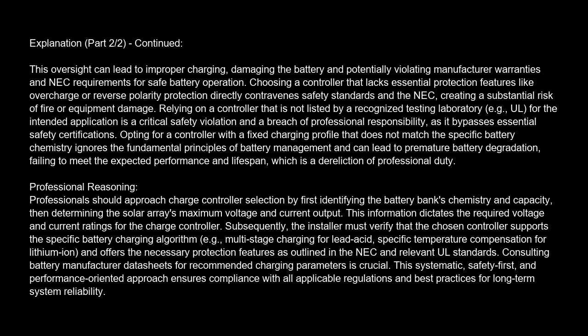Subsequently, the installer must verify that the chosen controller supports the specific battery charging algorithm, e.g., multi-stage charging for lead-acid, specific temperature compensation for lithium-ion, and offers the necessary protection features as outlined in the NEC and relevant UL standards. Consulting battery manufacturer datasheets for recommended charging parameters is crucial. This systematic, safety-first, and performance-oriented approach ensures compliance with all applicable regulations and best practices for long-term system reliability.